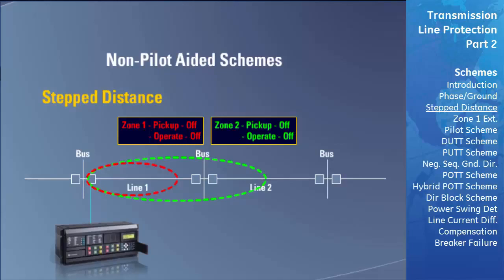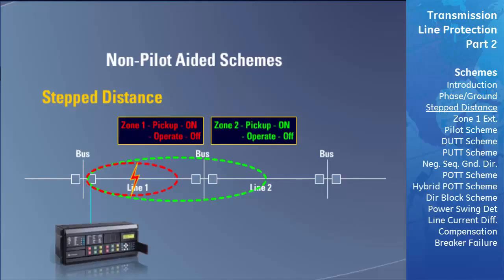Any faults at the beginning of the transmission line will be picked up by both zone 1 and zone 2. Since zone 1 has no intentional time delay, its operate flag turns on immediately. The zone 2 operate flag will not yet turn on because of its programmed time delay. Zone 1's operate flag triggers the relay to trip and clear the fault. At that point, the zone 1 pickup and operate flags turn off, the zone 2 pickup flag turns off, and the zone 2 operate flag remains in the off state, never having turned on.